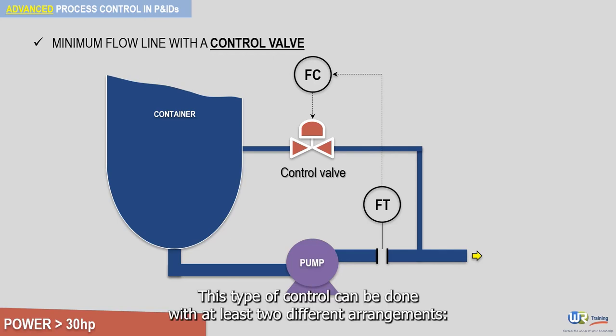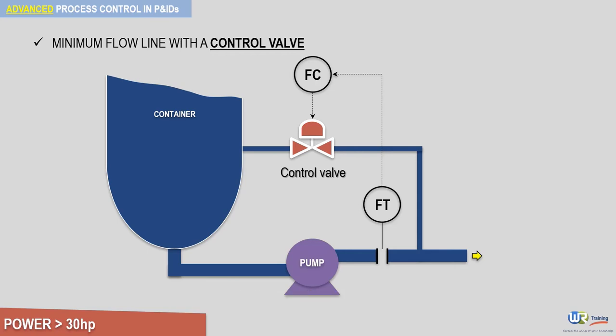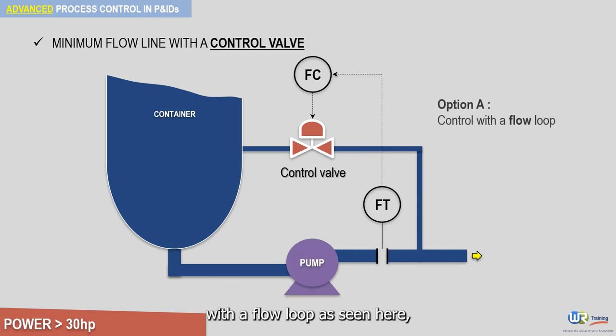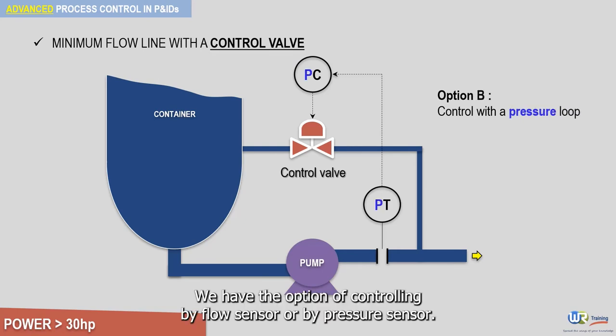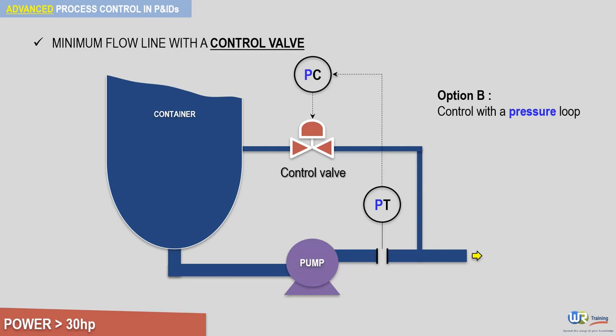This type of control can be done with at least two different arrangements: with a flow loop as seen here, or with a pressure loop. We have the option of controlling by flow sensor or by pressure sensor. Usually, the flow loop is selected.